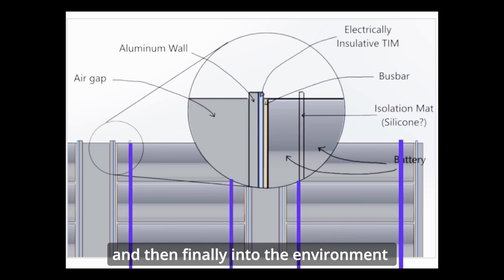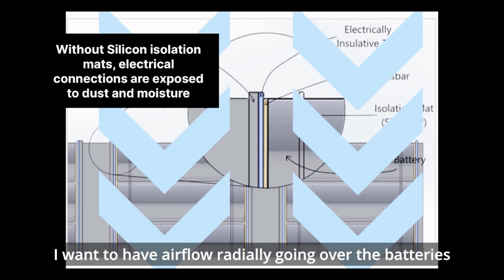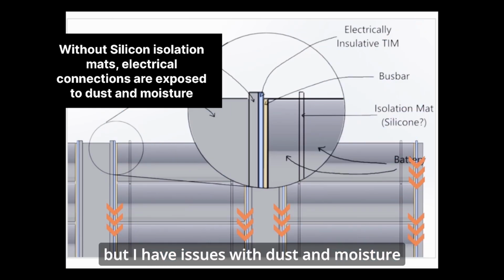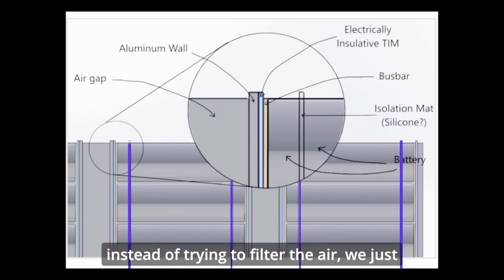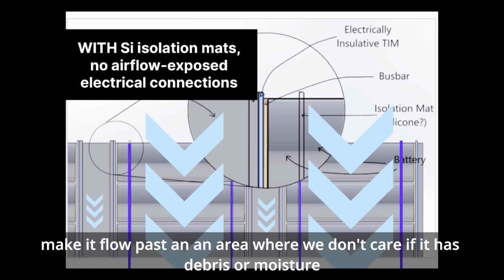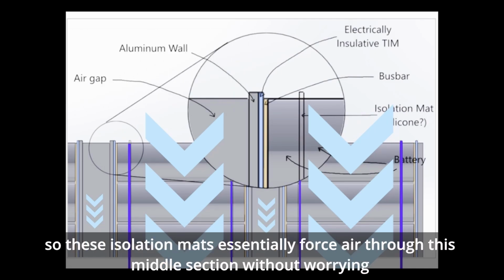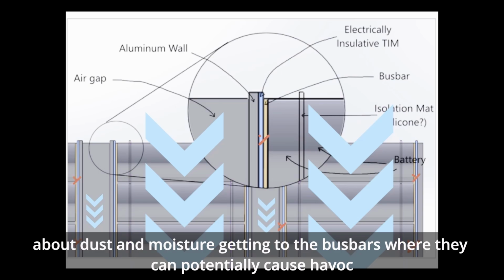The silicone mats have exactly one purpose. I want to have airflow radially going over the batteries, but I have an issue with dust and moisture. Instead of trying to filter the air, we just make it flow past an area where we don't care if it has debris or moisture. So these isolation mats essentially force air through this middle section without worrying about dust and moisture getting to the bus bars where they could potentially cause havoc.